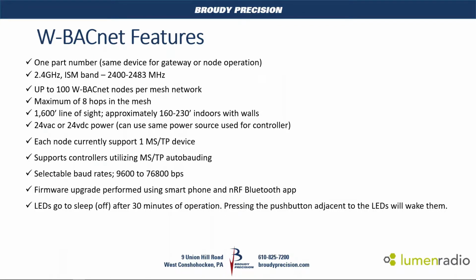Some of the features with the W-BACnet: there's one part number, and you do a switch selection for gateway mode or node mode. It's 2.4 gigahertz, and again, you can have up to 100 W-BACnet nodes per mesh network, and it's capable of 8 hops from one device to go all the way back. So you've got to watch the hops in the network. The distances allowed are roughly 1,600 feet in line of sight, and 160 to 200 feet indoors with walls. Again, it's going to depend on if it's a block wall, if it's steel, if it's wood, but still roughly 160 to 230 feet.